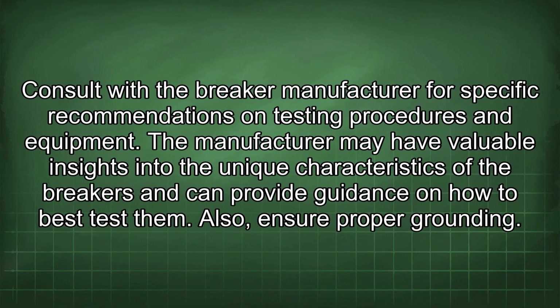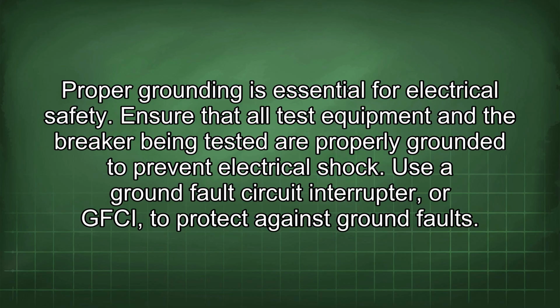Consult with the breaker manufacturer for specific recommendations on testing procedures and equipment. The manufacturer may have valuable insights into the unique characteristics of the breakers and can provide guidance on how to best test them. Also, ensure proper grounding. Proper grounding is essential for electrical safety. Ensure that all test equipment and the breaker being tested are properly grounded to prevent electrical shock. Use a ground fault circuit interrupter, or GFCI, to protect against ground faults.